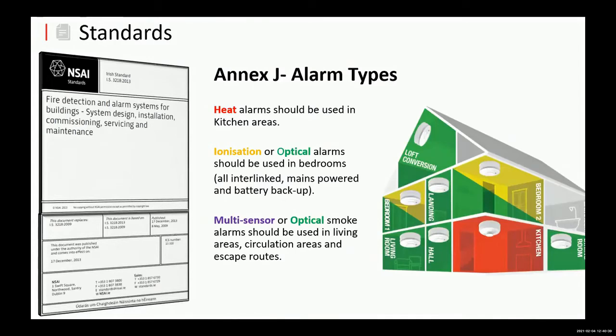So again, that's just a graphic of Annex J in relation to what's recommended under the IS 3218 standard. You get an option there in the bedroom area, and the reason the option is there is en suites. Just for example, an en suite. If you have an en suite in the bedroom, you're better off using ionization. If you don't, you're better off using optical. But the one thing I'd say about ionization, they're probably on their last legs at the minute. They will be phased out over the next period of time in the not too distant future. Most of our competitors at the minute don't supply an ionization detector because of the radioactive source. It's an environmental thing. There's licenses involved. There's extra costs in relation to transport. All that kind of stuff is going on as well. So we're looking at phasing out the ionization type detection. If you look at our new 3000 series devices, we don't have an ionization detector there. We do have a multi-sensor, which is replacing that.